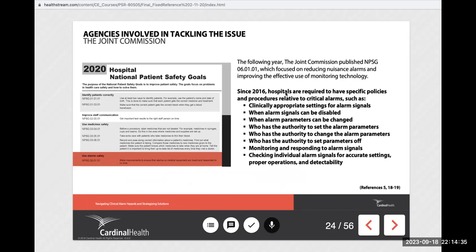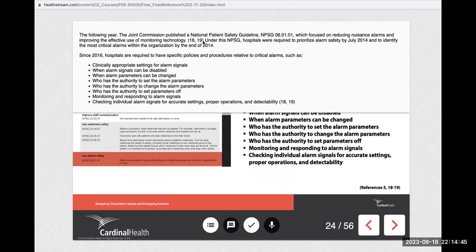Under this NPSG, hospitals were required to prioritize alarm safety by July 2014 and to identify the most critical alarms within the organization by the end of 2014. Since 2016, hospitals are required to have specific policies and procedures relative to critical alarms, such as clinically appropriate settings for alarm signals, when alarm signals can be disabled, when alarm parameters can be changed, who has the authority to set the alarm parameters, who has the authority to set parameters off, monitoring and responding to alarm signals, checking individual alarm signals for accurate settings, proper operations, and detectability.